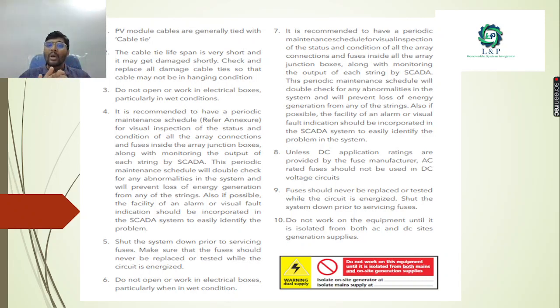Do not open or work in electrical boxes, particularly in wet conditions. And most importantly, cable ties have a lifespan. If they get damaged, please check and replace the cable ties. Always do periodic maintenance, and also monitor everything in the SCADA if it is a very big system. Do not work on the equipment unless it is isolated from both the AC and the DC side. And most importantly, if any fuses are blown, please replace them.